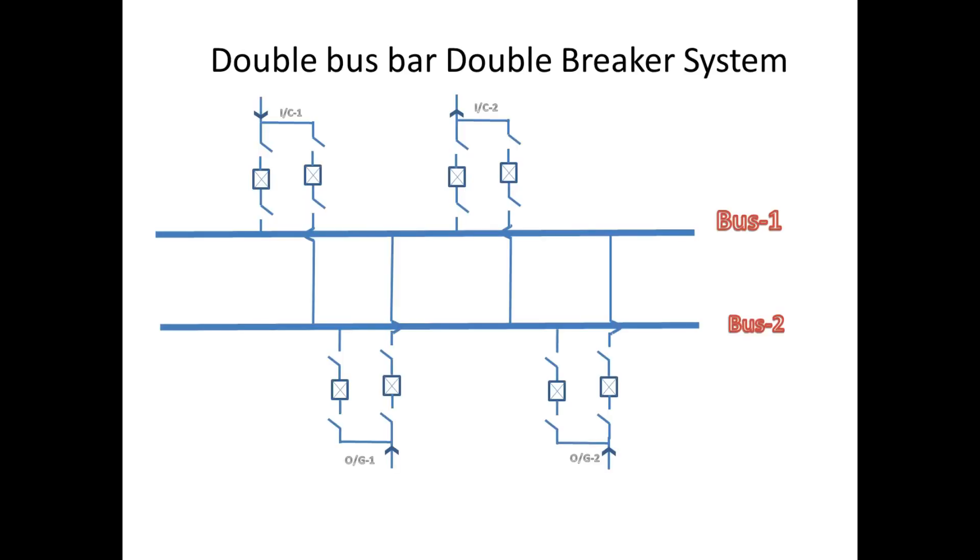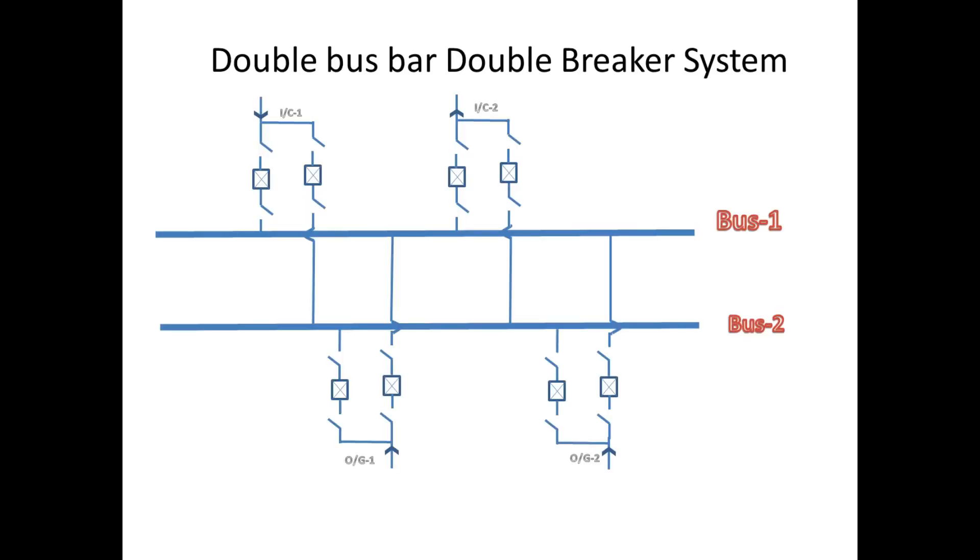In double bus double breaker arrangement, the feeders are connected in parallel to both buses with the help of two circuit breakers and four isolator switches instead of a bus coupler.